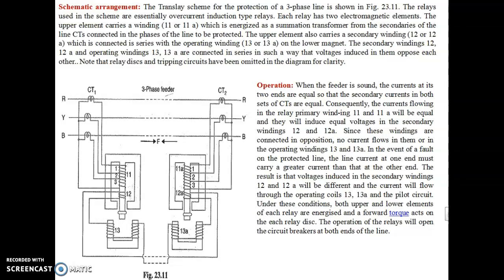Okay, so there is no relay energized; no torque is produced in the lower magnet at the normal condition and at the external fault condition. Is it clear? At the normal condition, or when an external fault occurs, usually the current flows in the primary winding of the upper magnet. Next, it produces secondary current at the secondary winding. So the secondary current flows through the secondary winding of these two, which is connected in series opposition with the operating coil. Hence at the normal condition and at the external fault, there is no current flowing in this operating coil. If no current flows in the operating coil, there is no torque produced here. No torque is produced here, only at the upper magnet. Hence there is no interaction of these two fluxes, no interaction of these two torques. Hence there is no operation of the relay here.